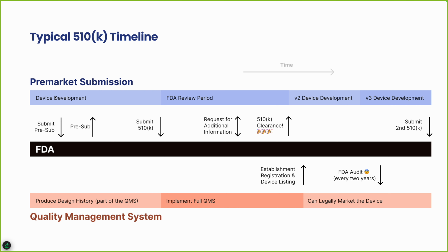So as you're building your device, you may decide that you want to interact with the FDA, ask them questions. Often this is about the design of any clinical studies that you're doing to support your device, to make sure they agree with the approach before you spend significant money on doing the study. But then, you'll put together all the documentation, do all the testing, cybersecurity testing, and so on.